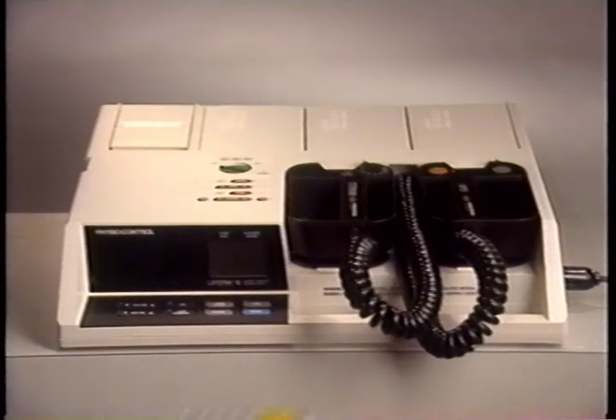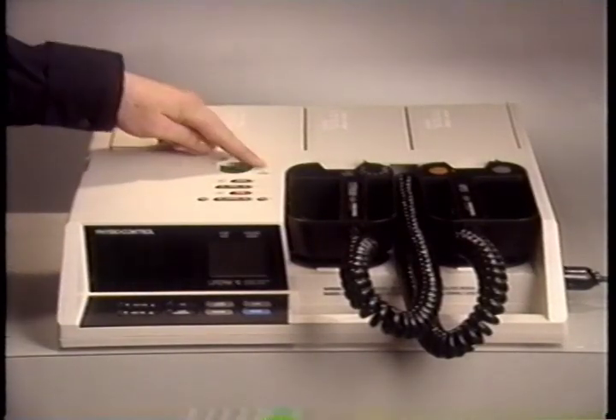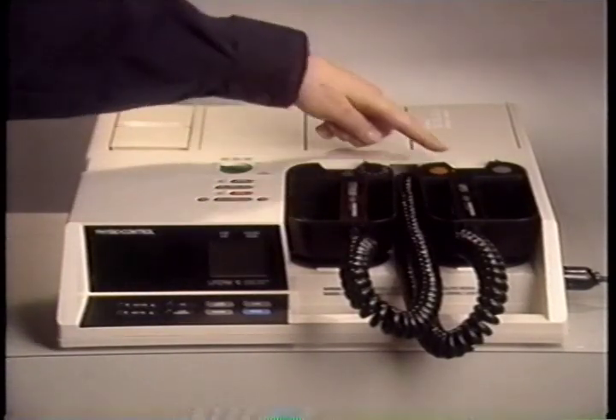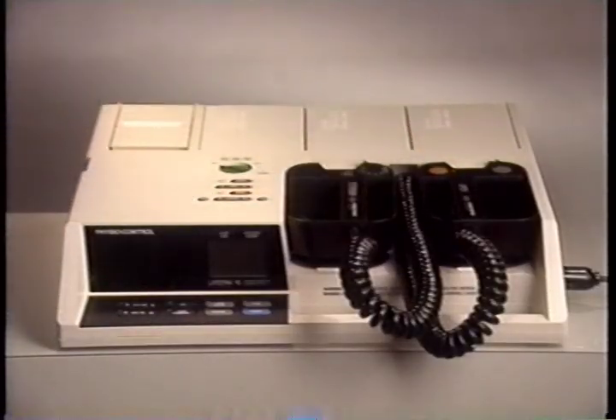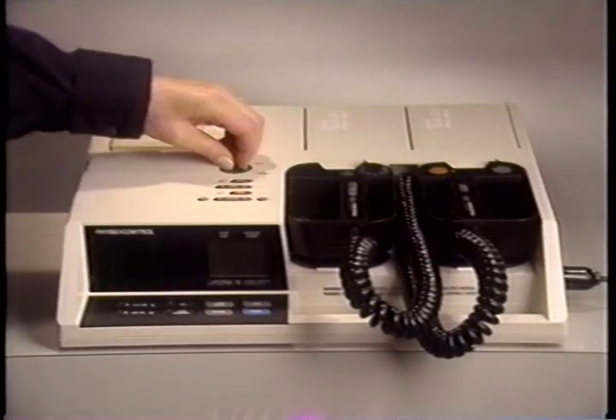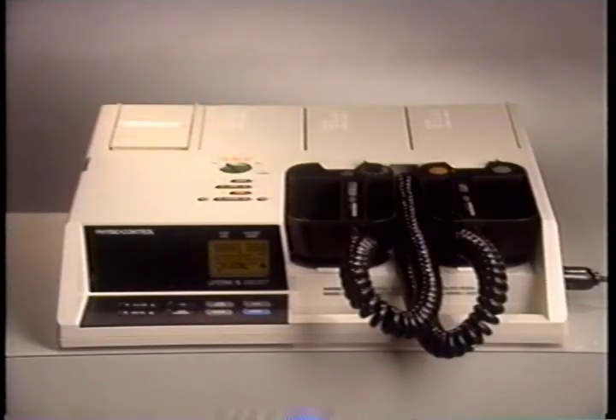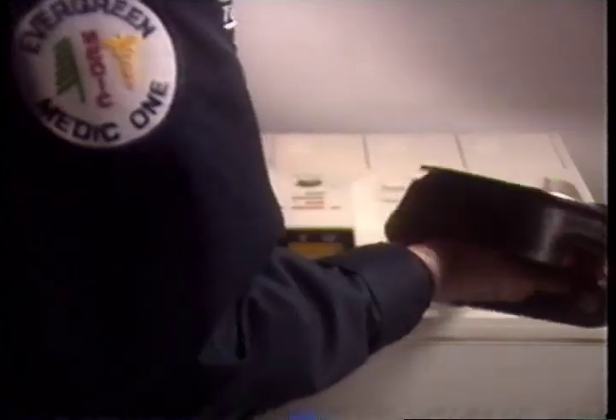As with other Physio-Control defibrillators, the controls are labeled 1, 2, 3 to guide the user quickly through the defibrillation procedure. Number 1, turn the power on and observe the patient's ECG signal either through paddles or ECG electrodes. Remove the paddles from their wells by sliding them back. Apply defibrillation gel to the paddles.